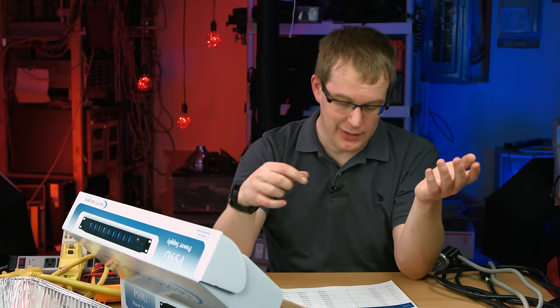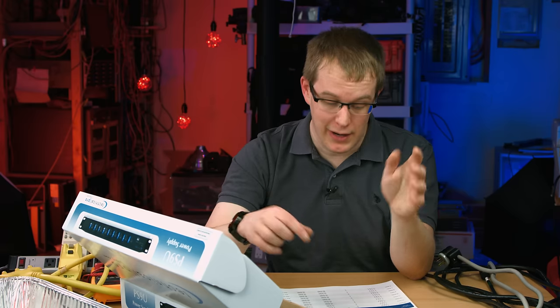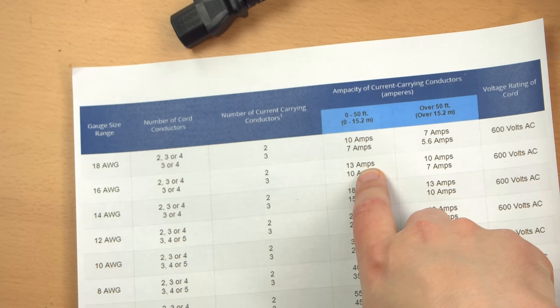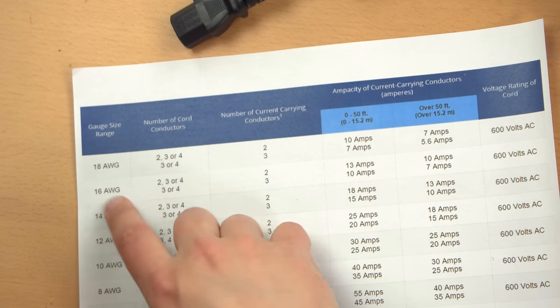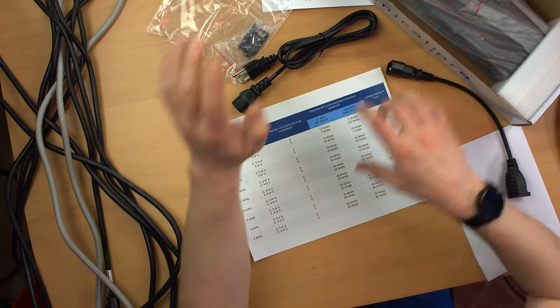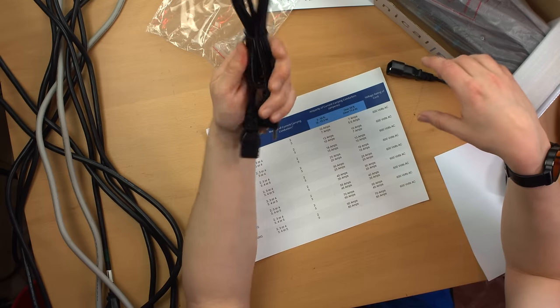So for this PDU, I would want a 14 gauge cable because that has an ampacity rating of 18 amps. 15 is less than that, that's fine. The next smallest conductor size would be 16 gauge, only rated at 13 amps. We want a 15 amp rated cable for this. So right away, I wouldn't throw this out personally. I would use this for something else that I know is going to be low current.